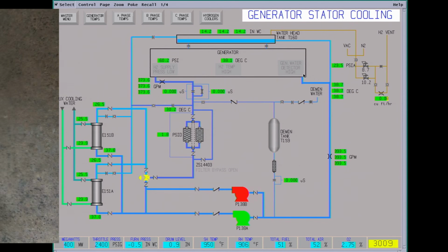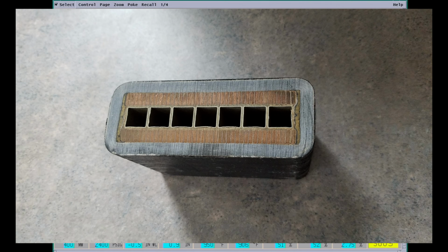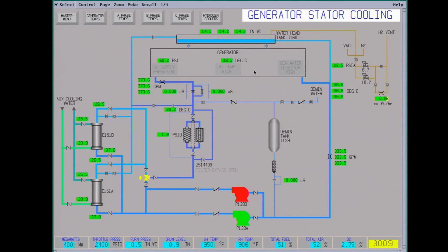There's like Tygon tubes that put the water right into the windings. The windings are hollow square tubes, so the water will circulate through and pull a lot of the heat out. That's why the water has to be so pure. If there's any minerals in the water, it can conduct electricity. The windings on this unit run about 24,000 volts.